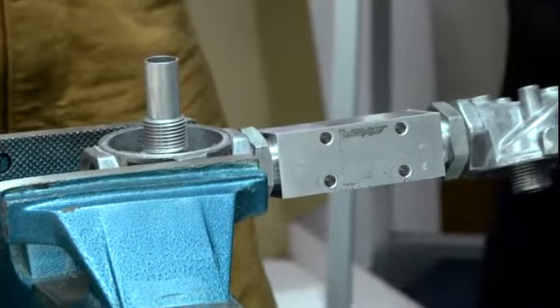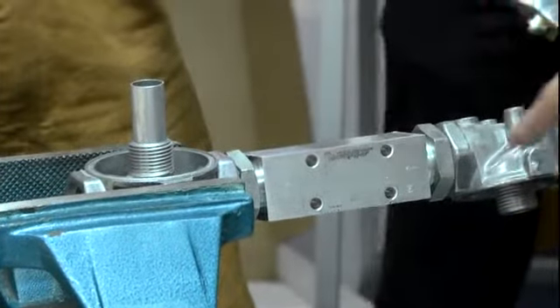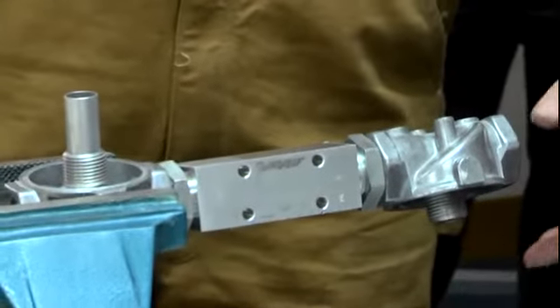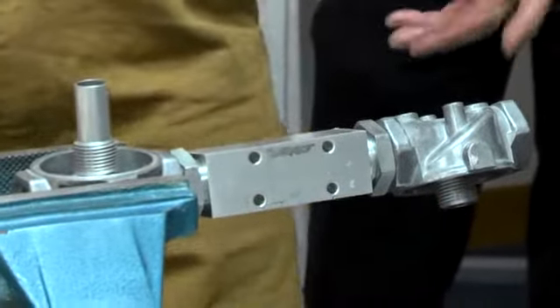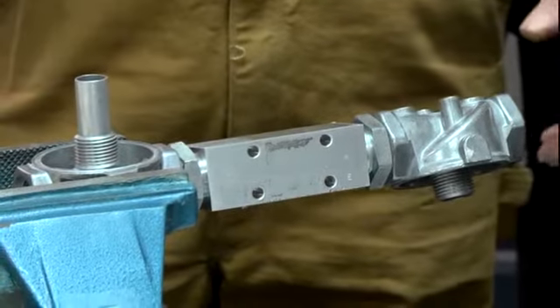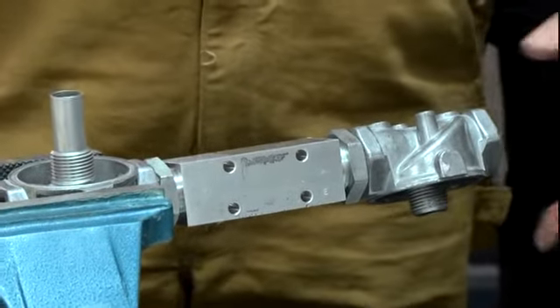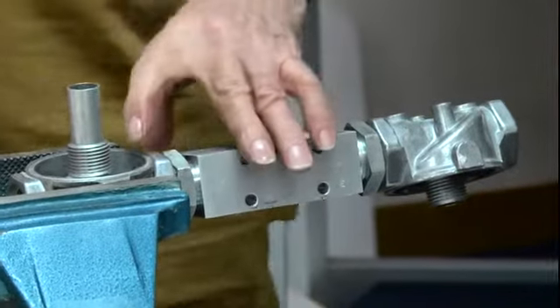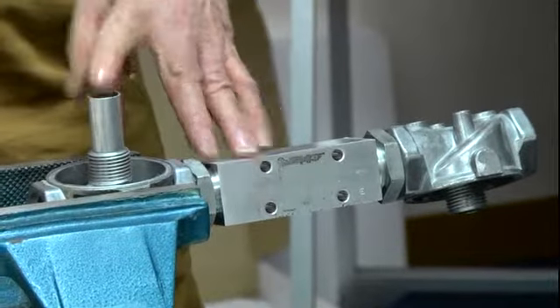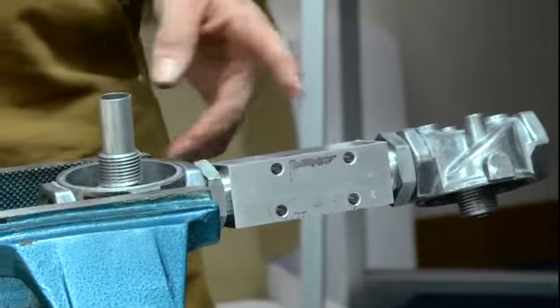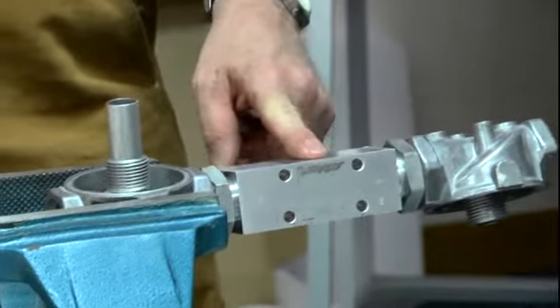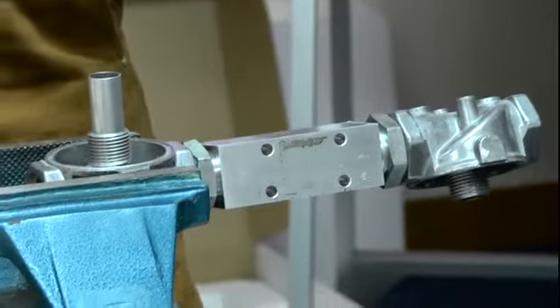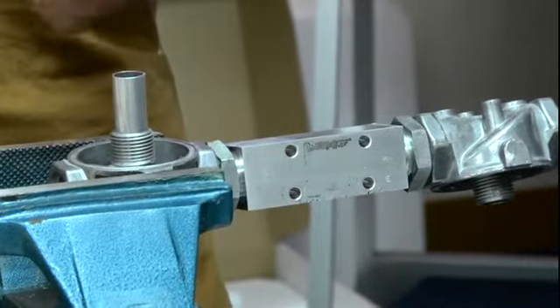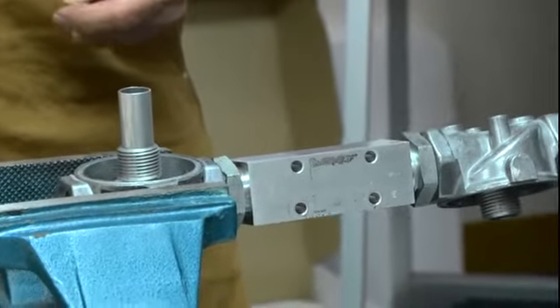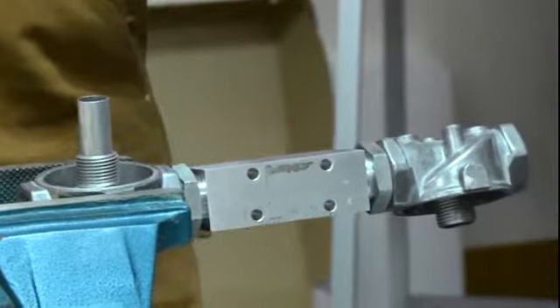Anybody want to try it? Why does it have to go to the opposite side? Right. The flow homogenizers always point down, but like I say, you can have it up to 20, 25 degrees. You can go a little bit further, but we want to keep it no more than that. The pulsation damper is important to have as perpendicular as possible against the block, because we want to trap the maximum amount of air up there, the maximum amount of vapors or gases. We want that bubble to be as big as possible.